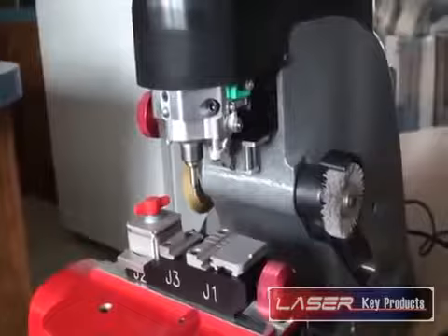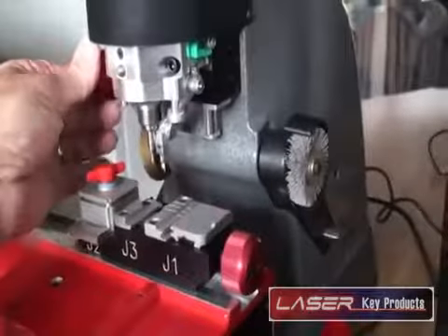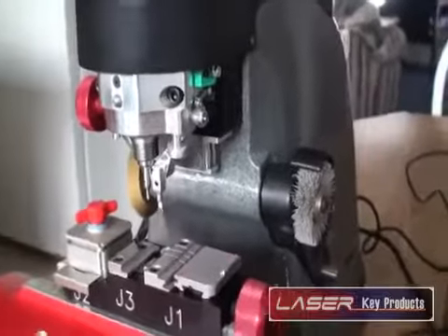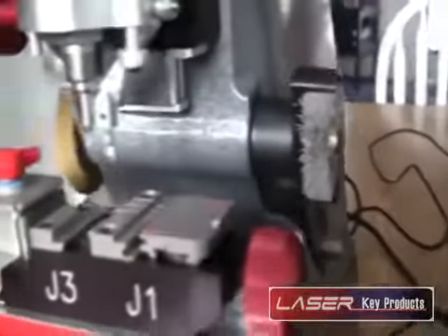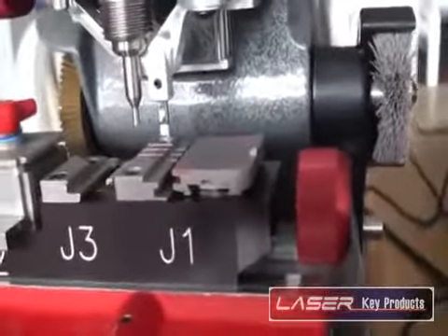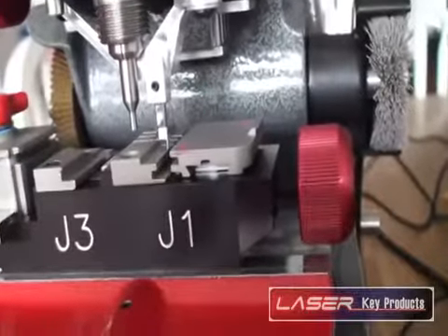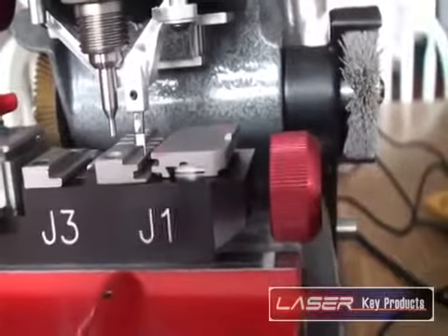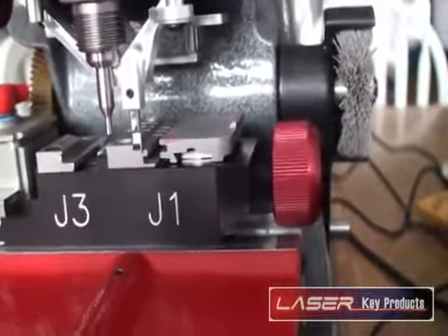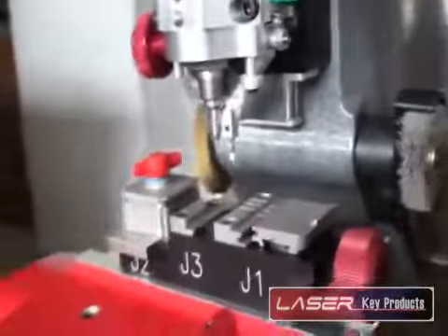The next thing we're going to do in completing the calibration process is lower your tracer tower down, and go to your software and say operations, calibrate tracer, and again this is jaw 1, so put number 1 and click OK. Again, the machine will go into the process of coming down, touching off, going right, touching off, coming forward and now shifting over, and touching off. It goes back to the home position, which you should always do. Again, a 30-second process here. And once it's done, we click OK.